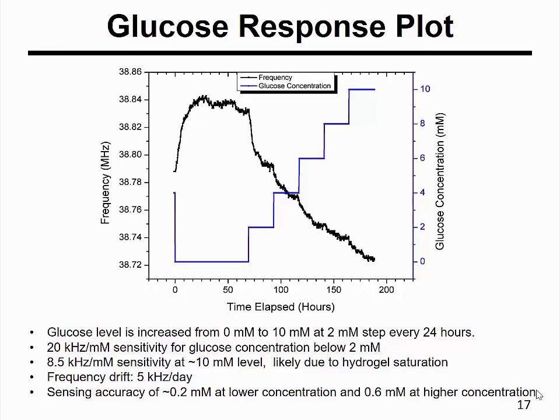And what's more important in this plot is actually this part. So when I don't have any glucose change, you can see there is a frequency drift, and here I show 5 kilohertz per day frequency drift, even though glucose is not changing. So this drift is limiting our sensing accuracy, and I will talk about why we have this drift and how to eliminate it. So with this drift, we achieved a 0.2 millimole at lower concentration and 0.6 millimole at higher concentration sensing accuracy, in other words, resolution.